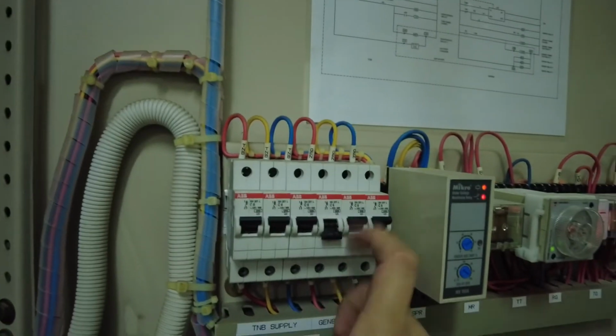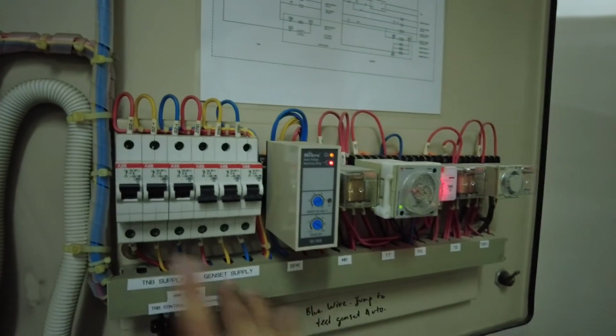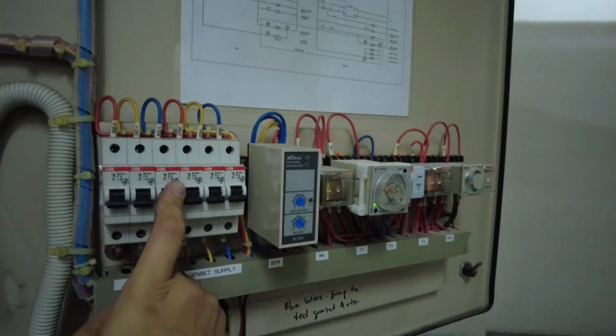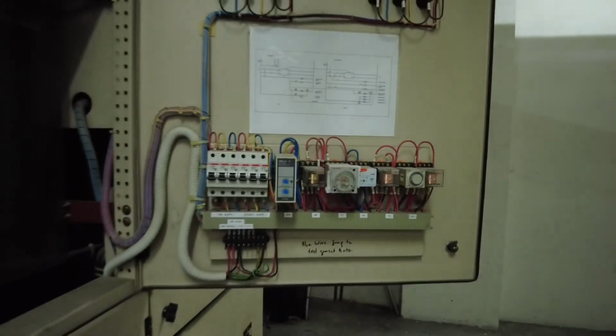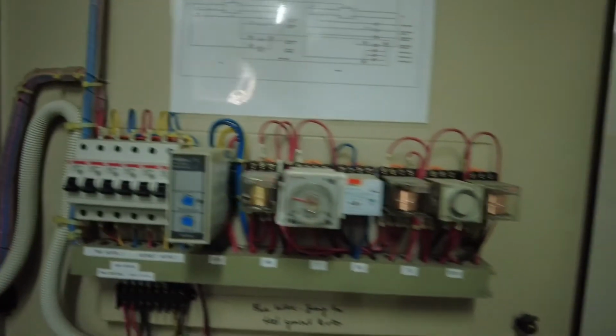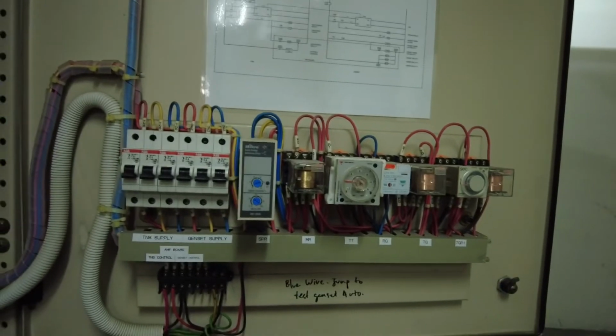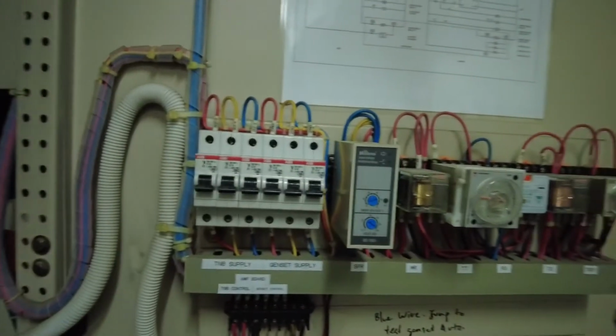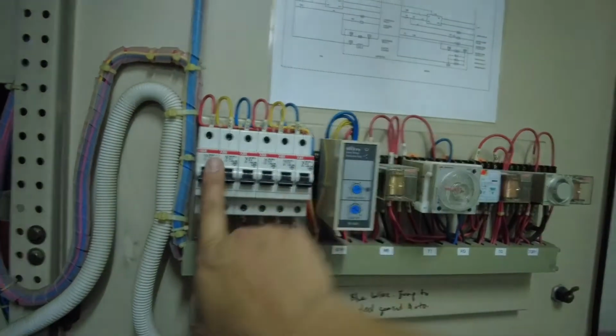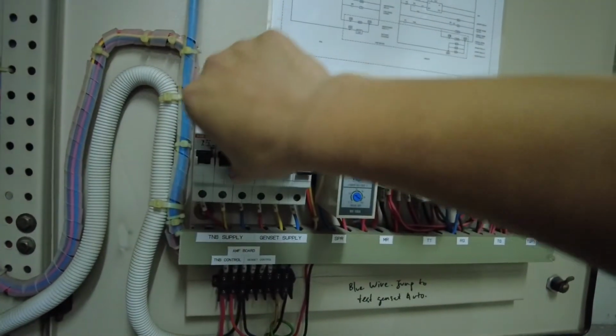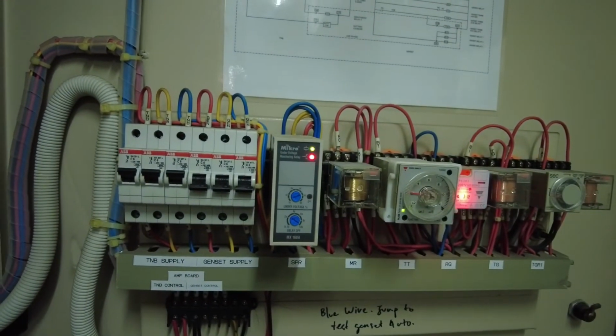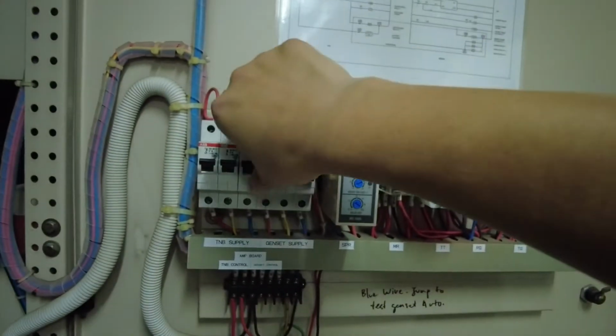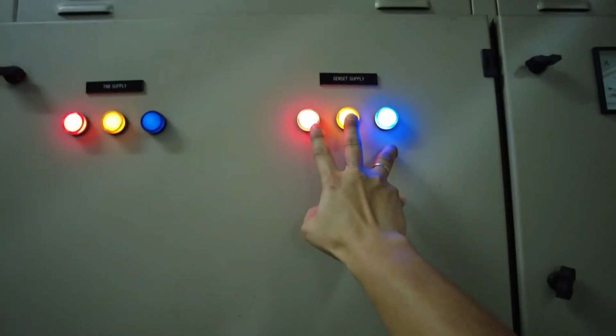As usual, off the genset MCB first. Then trigger this by turning off the main supply MCB. Allow a few seconds, because the genset takes around 5 to 6 seconds to start up and reach full speed. Now on back the main supply MCB to allow this to operate first. Once this operates, then only you on back the genset MCB. Here you can see, the genset is running already.